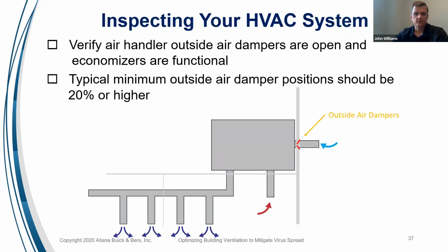One of the most basic items to inspect is that your outside air dampers are open. I think we've kind of beat that horse to death here, but making sure that we're getting that outside air, we're bringing it in. Typical units, again, it really varies by location and by application, but typically 20% of your volume of air is coming from the outside. So if you go up there and you find a unit that's running and the outside air damper is closed, you should be asking the question of why. Why is this closed? Why don't we have outside air?